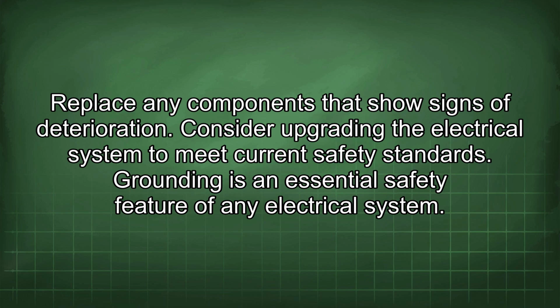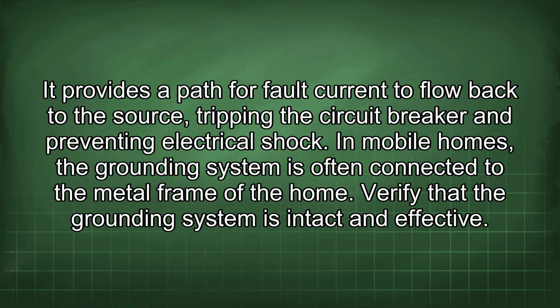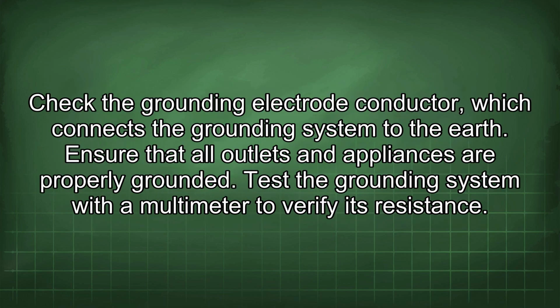Grounding is an essential safety feature of any electrical system. It provides a path for fault current to flow back to the source, tripping the circuit breaker and preventing electrical shock. In mobile homes, the grounding system is often connected to the metal frame of the home. Verify that the grounding system is intact and effective. Check the grounding electrode conductor, which connects the grounding system to the earth. Ensure that all outlets and appliances are properly grounded. Test the grounding system with a multimeter to verify its resistance.